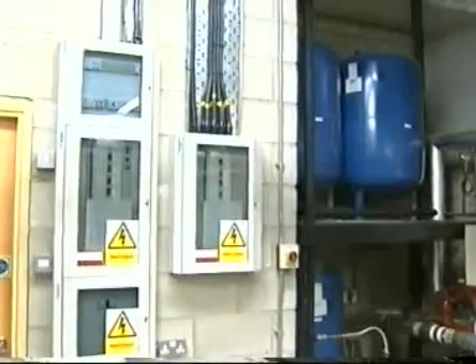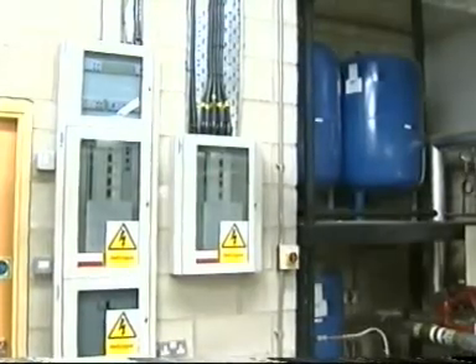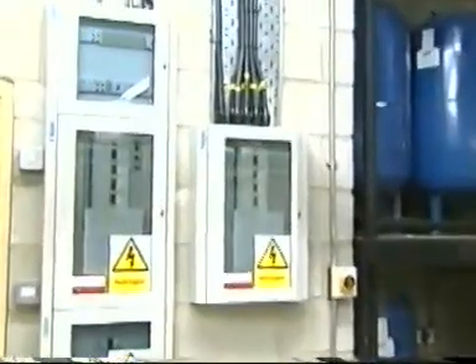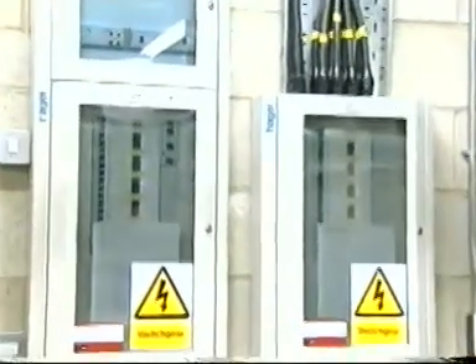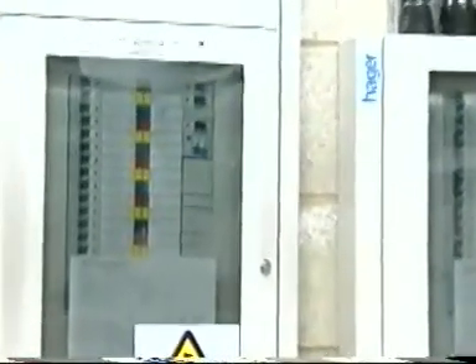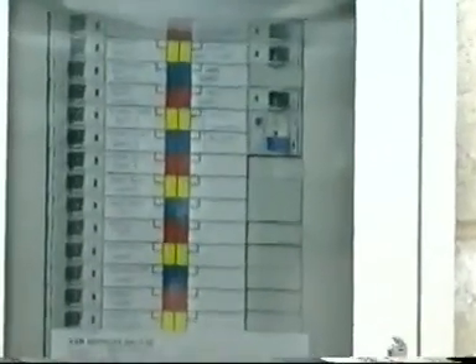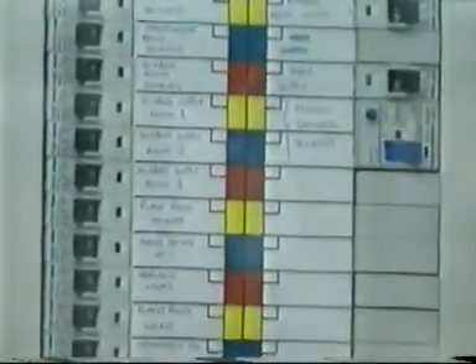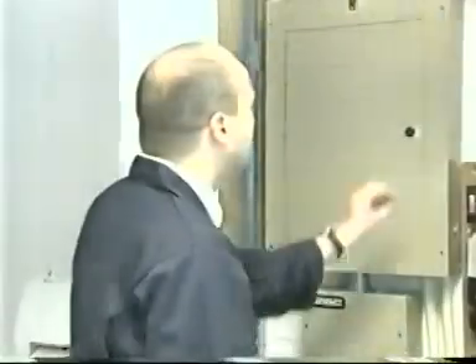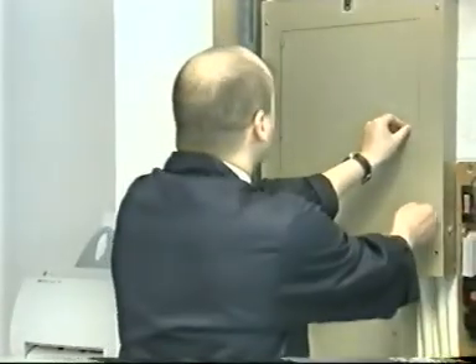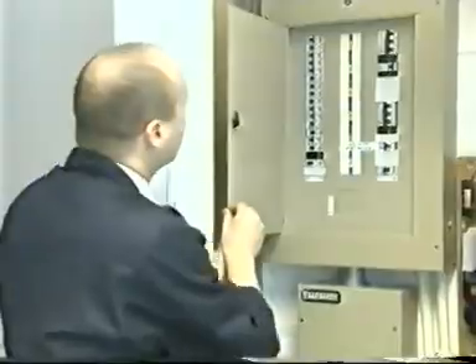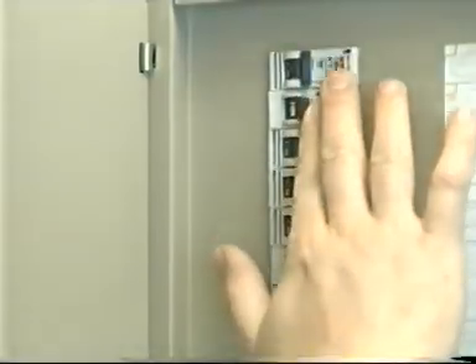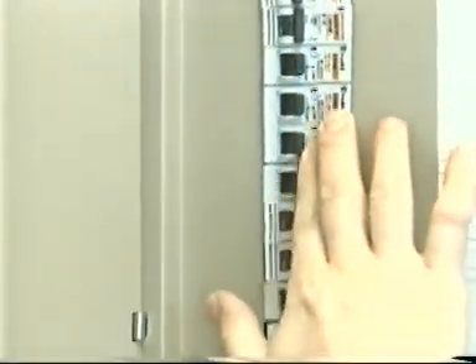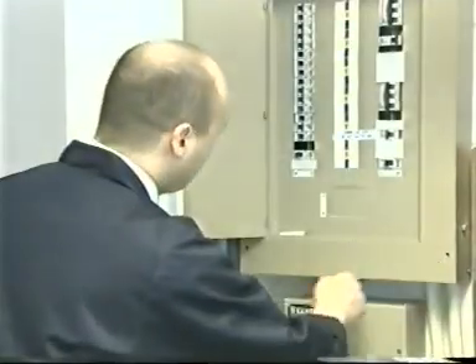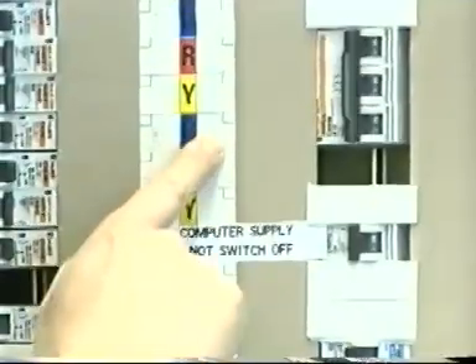The verifier, together with the user, must have information identifying the purpose of circuits, together with fuse and circuit breaker ratings. It's therefore important to ensure the installation is properly equipped with labels and notices outlined in the regulations. The word inspection embraces human senses including sight, touch, hearing and smell. Such senses, where practicable, are used to carry out inspection before and as necessary during testing.